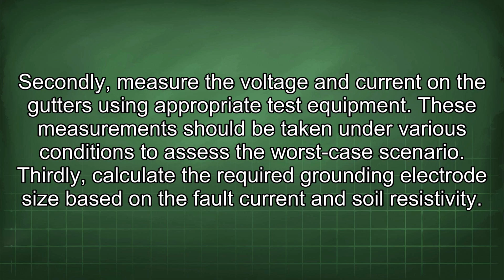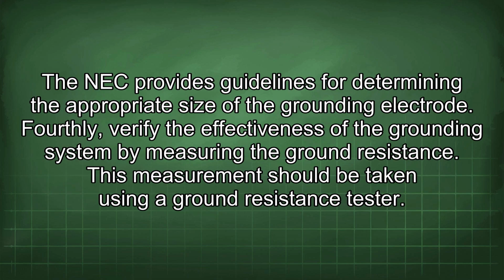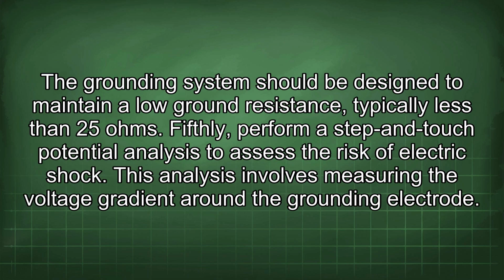Thirdly, calculate the required grounding electrode size based on the fault current and soil resistivity. The NEC provides guidelines for determining the appropriate size of the grounding electrode. Fourthly, verify the effectiveness of the grounding system by measuring the ground resistance. This measurement should be taken using a ground resistance tester. The grounding system should be designed to maintain a low ground resistance, typically less than 25 ohms.